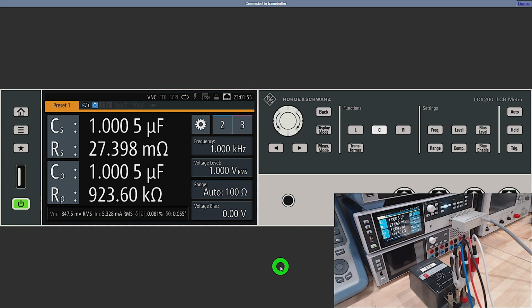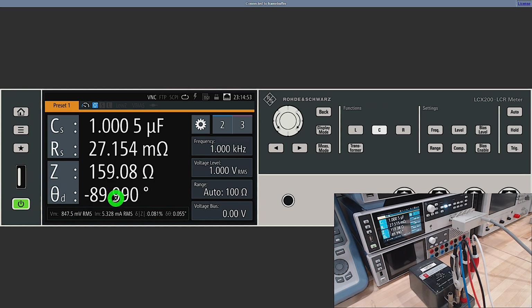Now let's play with the settings of the instrument and see how it affects the measurement. First of all, I changed this to impedance and phase. If you look at the phase, minus 89.99, essentially minus 90 degrees, it means that we are very far away from the self-resonance of this capacitor, and we can rely on this capacitor's measurement and the equivalent model here. In fact, this capacitor is rated for over 10 kilohertz, and that makes sense because we're only at 1 kilohertz here.